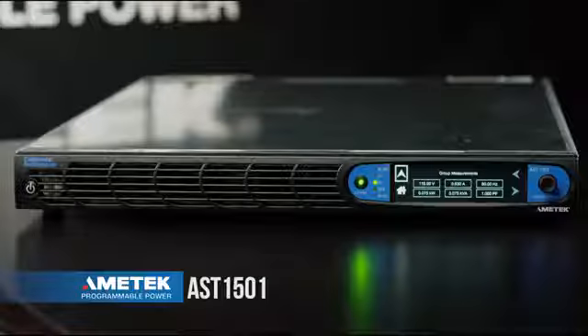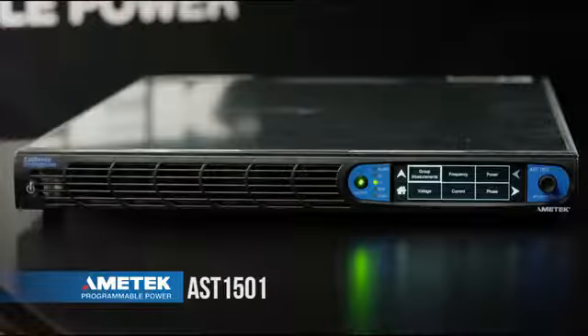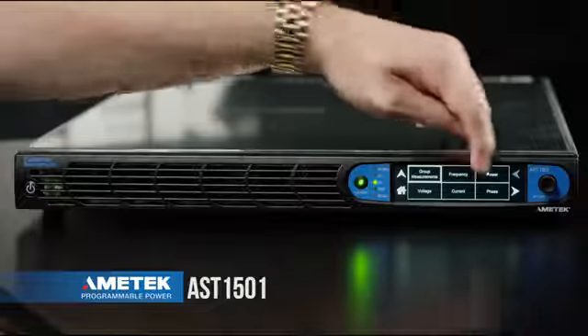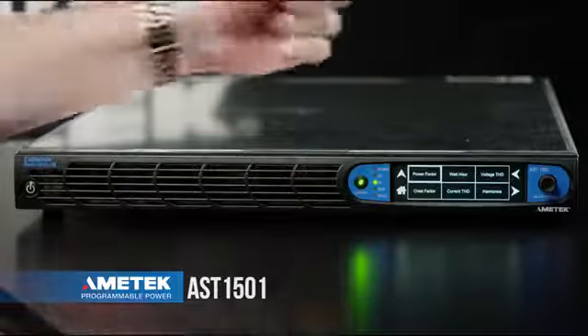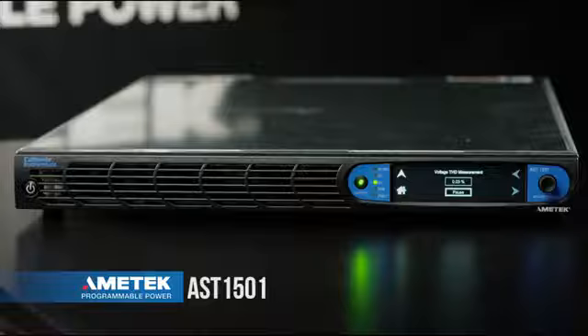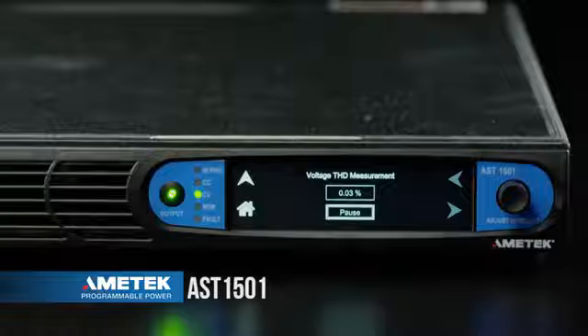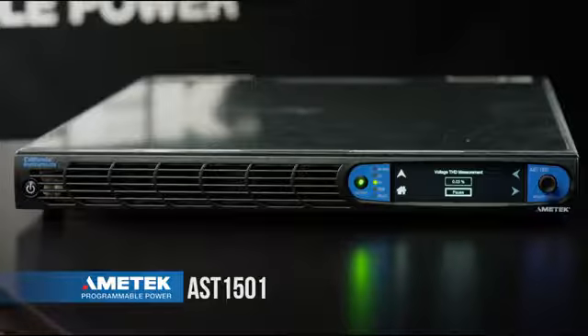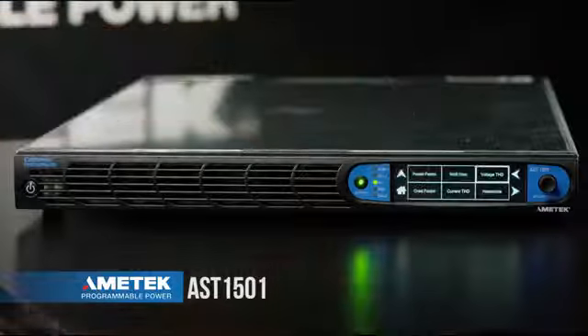Going back up to our prior menu, we can select other measurements such as voltage harmonic distortion, which is presently at 0.03%. There's a pause key on this display which allows you to capture a moving value that might be present if you have a dynamic load. Go back to our prior measurement screen.